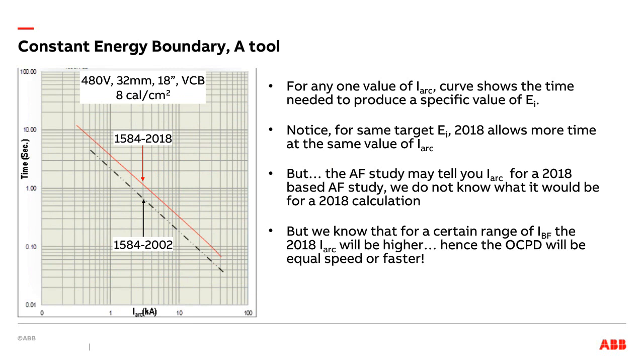There's a tool that people that deal with arc flash sometimes use for analysis, particularly when you don't have exact values of bolted fault current. And that is called the constant energy boundary. I mentioned it in a previous slide. Here's a constant energy boundary for 480 volts, 32 millimeters, 18 inches working distance, VCB. This energy represents 8 calories.